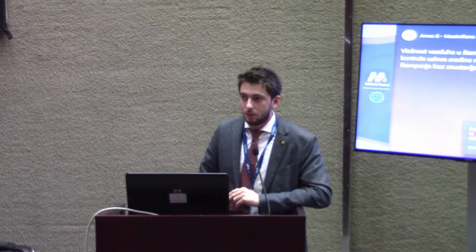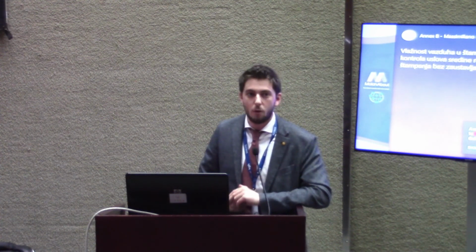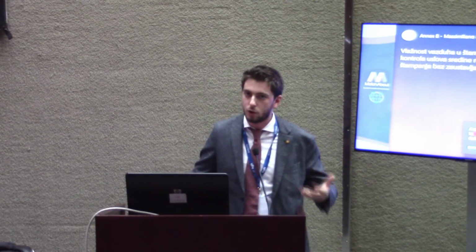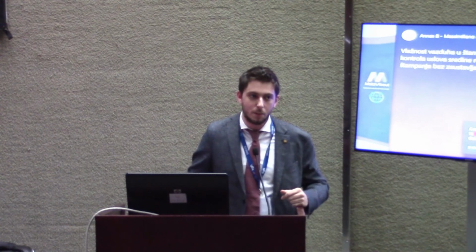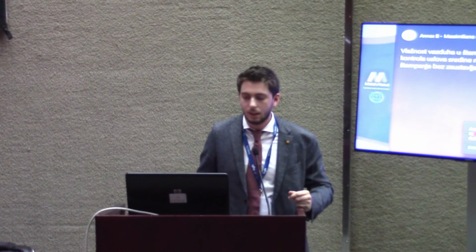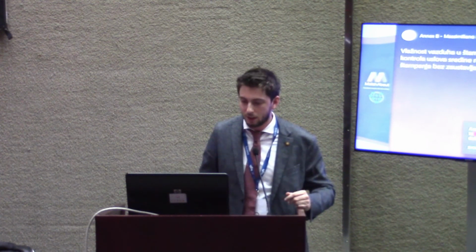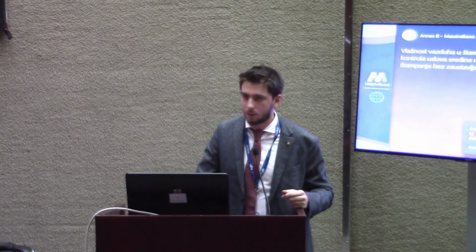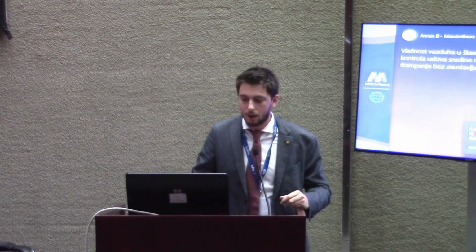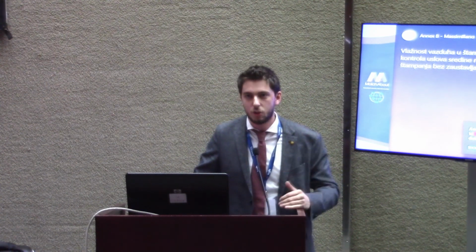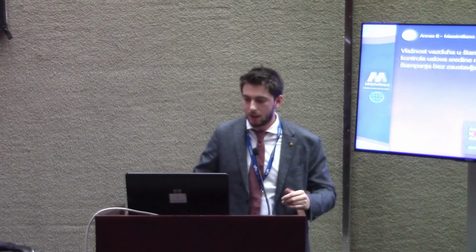Adiabatic humidification has the double advantage of both humidifying and cooling down the environment. So the production facilities usually have natural heat flow coming from the machine itself. So an adiabatic humidification might counter the heating provided by the machine itself. Of course, it is highly suggested to have professional support from the beginning from us or other companies that supply humidifiers in order to have the best support and understand which is the best trade-off for the specific case.